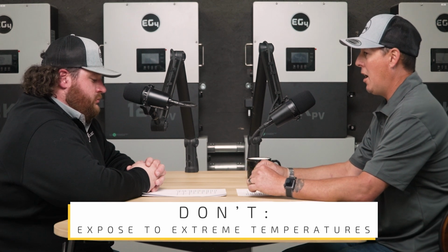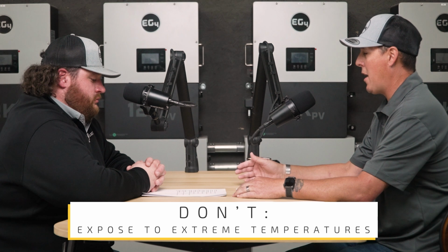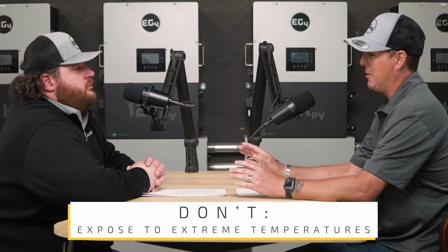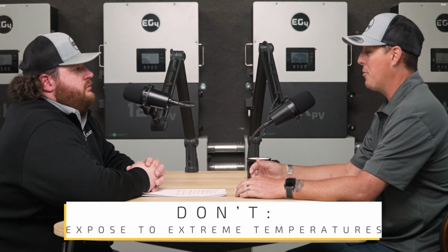This kind of caveats to that - don't expose to extreme temperatures. Any manufacturer in the world of solar inverters and batteries will say right in the install manual - I'd bet on it, I know our equipment does - do not mount that in direct sunlight. I live in Arizona; if you were to put that on a south-facing wall in Arizona in the summertime at 118 degrees, you're going to start having electrical problems. It's either going to cook the inverter or you're going to start seeing some really weird stuff going on with that system - it may not function as designed. So make sure you're installing that under an eave, preferably on a north-facing wall - you're going to get the least amount of sun exposure in that world, being in the northern hemisphere. So make sure that we're doing that.